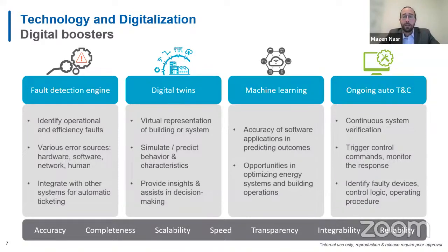We do that by having our system trigger control commands to various assets in the building, and we do that during non-operating hours, so we're not interrupting building operations. The system monitors the equipment's response and flags anything that could be due to faulty hardware, faulty communication, or control logic that doesn't make sense.